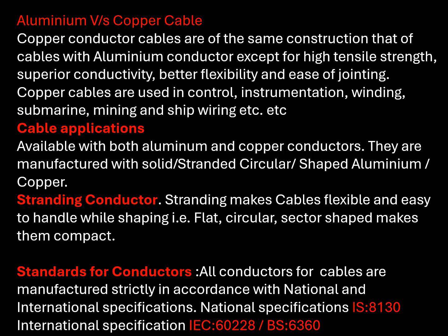Let us go into further detail on some more things necessary to understand. Aluminum versus copper cable. Copper conductor cables are of the same construction as cables with aluminum conductor, except for high tensile strength, superior conductivity, better flexibility, and ease of jointing. Copper cables are used in control, instrumentation, winding, submarine, mining, and ship wiring, etc.